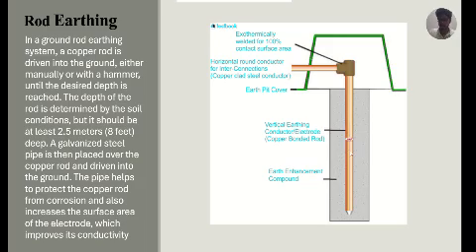The depth is usually around 2 to 3 meters, depending on the soil condition. This method is highly effective in rocky or dry soils where other earthing methods may not work well. Where other earthing methods are quite difficult, we use this kind of earthing. That's why we commonly use it in our residential buildings, telecom towers, substations, etc.